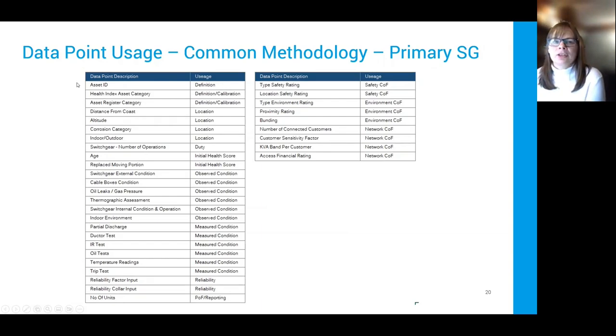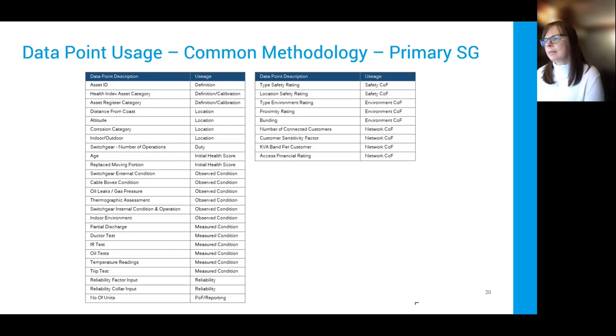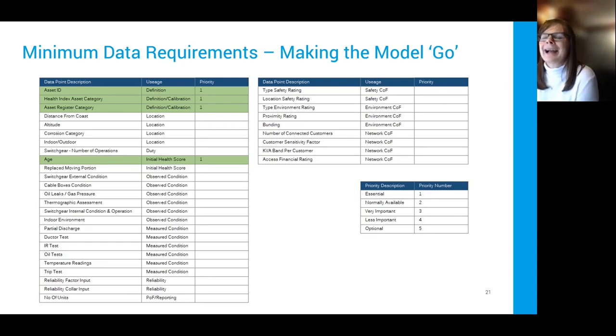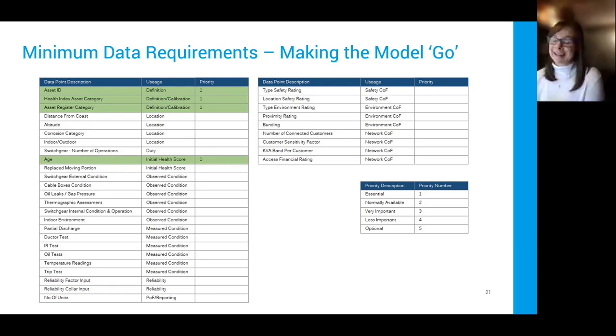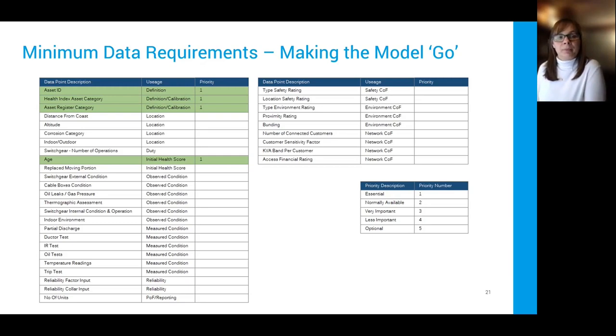This slide shows approximately where all those data points are used in the methodology. We've been doing analysis with network operators' data to look at what we'd consider the minimum criteria. For this particular methodology — an age modified by condition approach — age is the basis but condition is really important. An asset can only achieve a health score of 5.5 (about the midway point) if it has no condition information. Once condition information is available, we can move it further up the health index scale, but only if that condition information indicates poor condition.